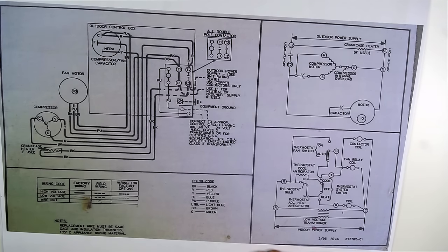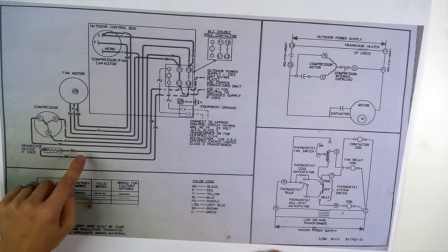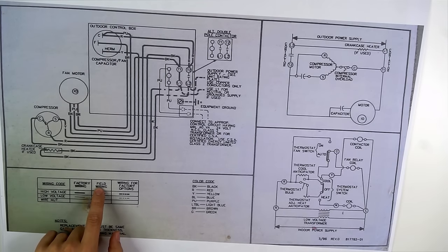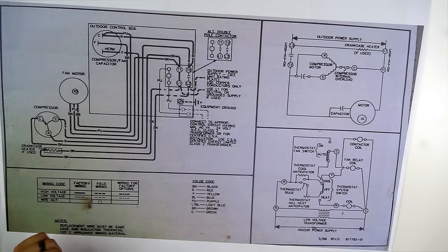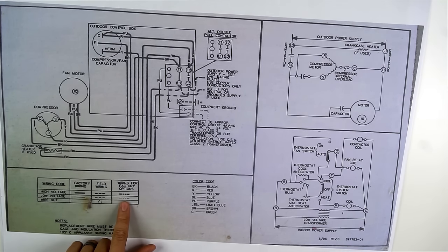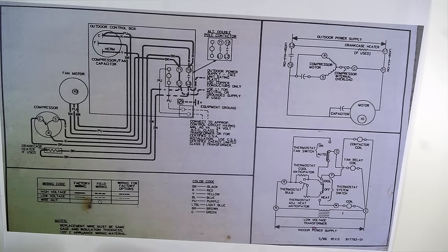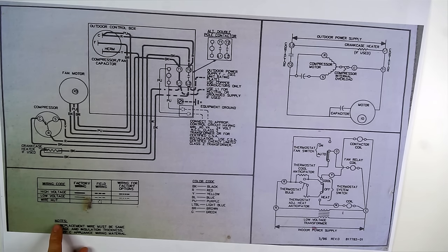Dashed lines mean those wires may or may not be in the unit. Factory wiring means the wires are already in the condenser unit — they come with it. Field wiring is wiring that has to be added or installed by the installer; these wires do not come with the unit. Wiring for factory options means those wires may or may not be there — for example, the unit might or might not have a start capacitor. There are also some notes on the bottom.